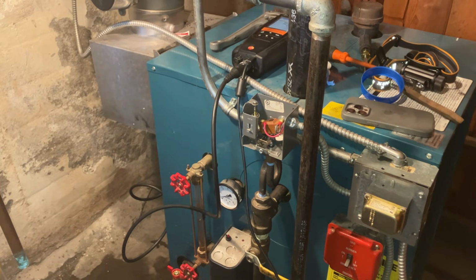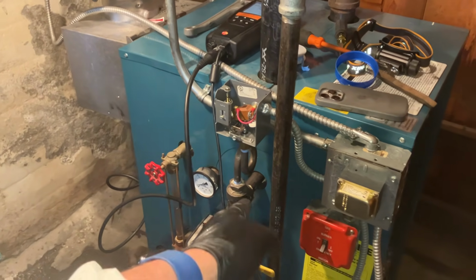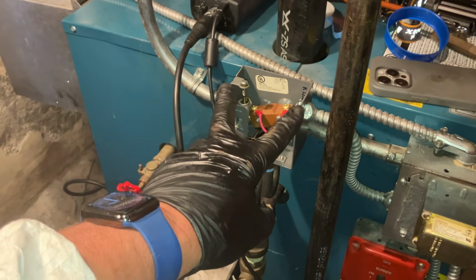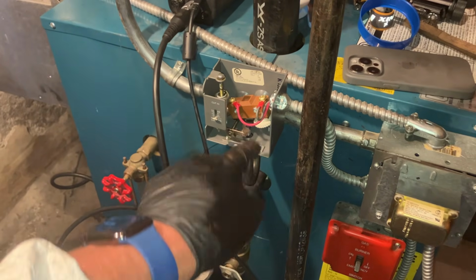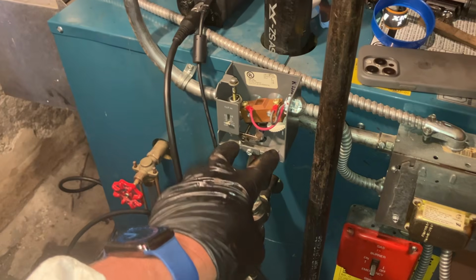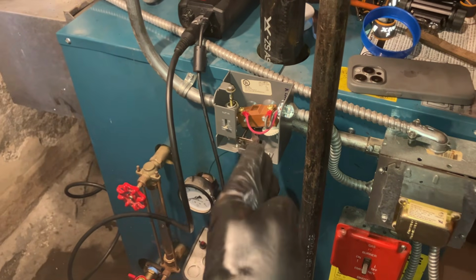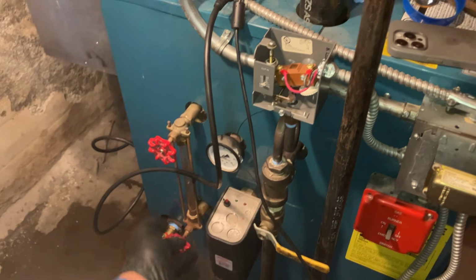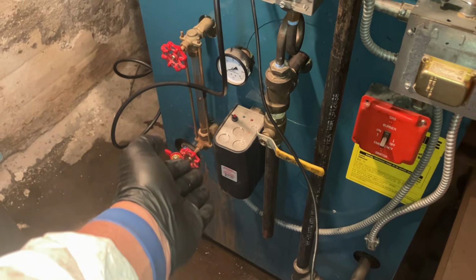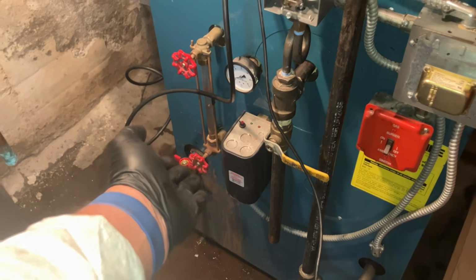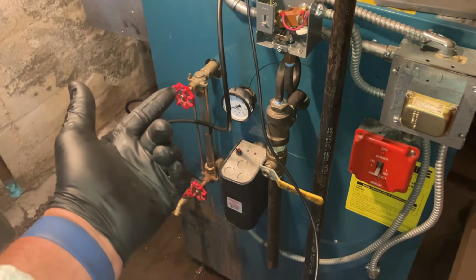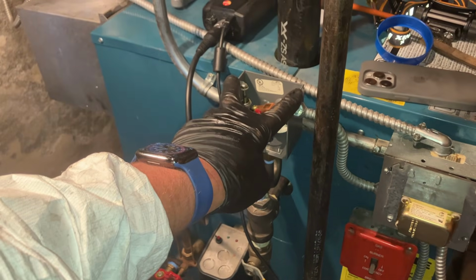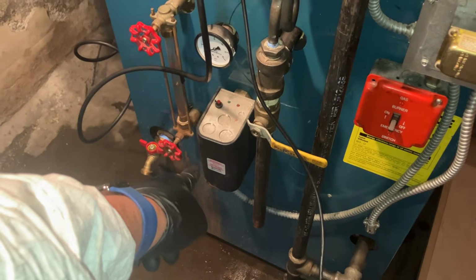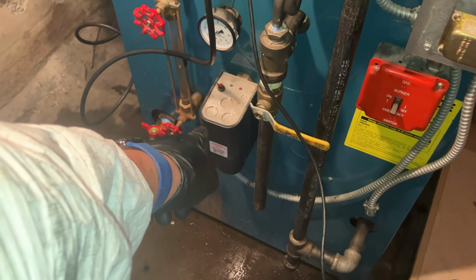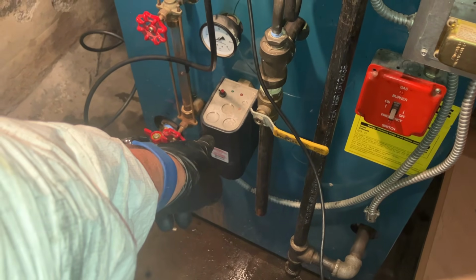And the safety circuit is a series. Okay, if one goes out, they all go out. So we're getting power across our Pressuretrol. So power goes in as long as the limit is closed. Continuity or power will pass through it. Then it'll go to the next safety, which is the low water cutoff. Could be low water cutoff, but there's multiple safeties here. We have a Pressuretrol to regulate pressure. We have a low water cutoff, which will prevent burner operation if there is insufficient water.